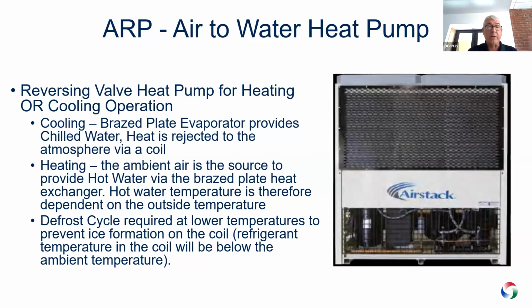When you're in heating mode, the reversing valve says, all right, I'm going to grab some of the ambient air. I'm going to transfer that into the hot water loop using the brazed plate heat exchanger. The temperature of the hot water is driven very much by the outside temperatures here. So one of our lessons learned along the way has been physics principles dictate that the colder it gets, the less heat you can move. However, we've developed some new technologies that use a technology called refrigerant injection that allow us to expand the compressor map and are able to do 130 to 135 degree hot water at 0 to -5 degrees Fahrenheit with an air-cooled machine. And we're continuing to work to make that even better because we know it gets a little chilly here in Colorado as it does in Wisconsin, and we're working to expand that capability.